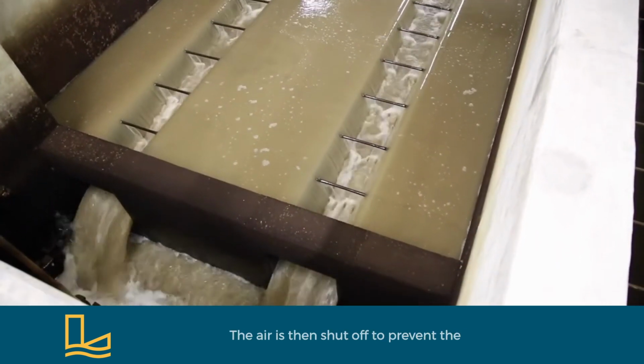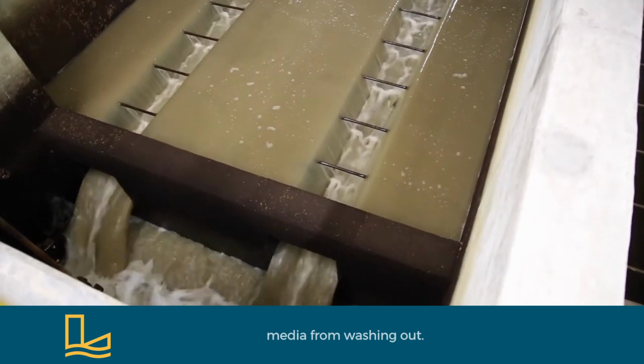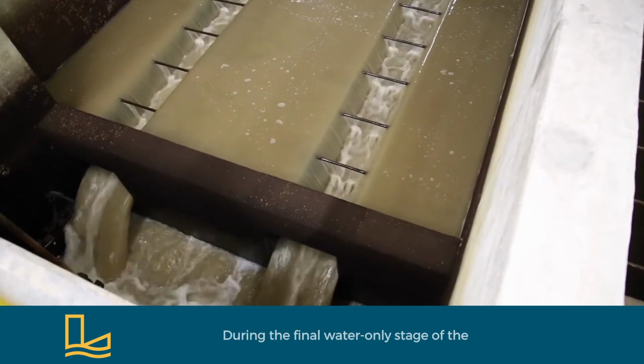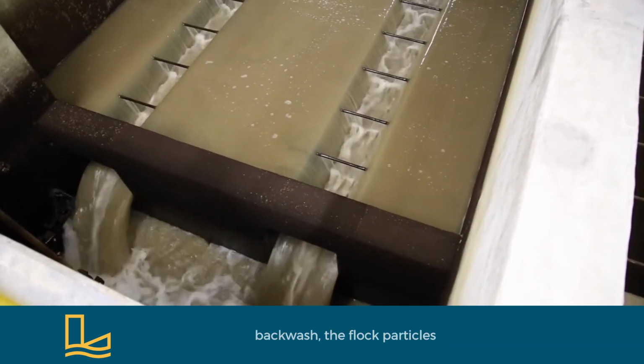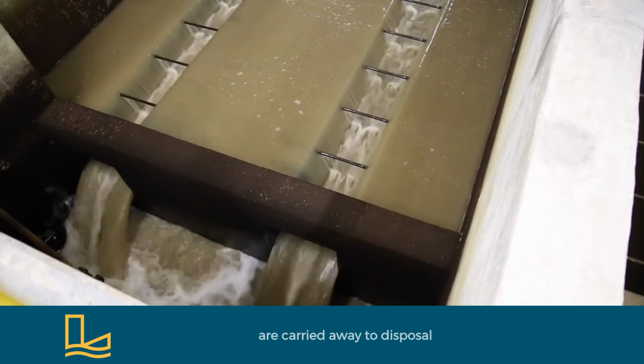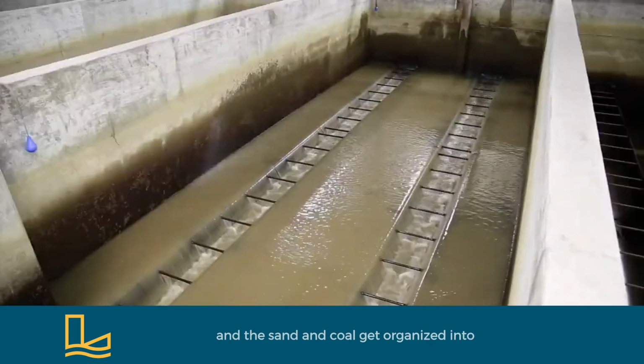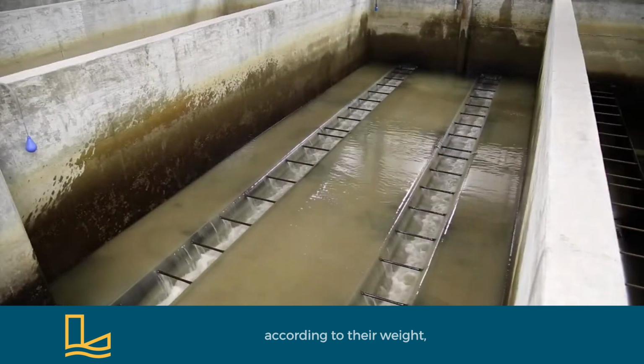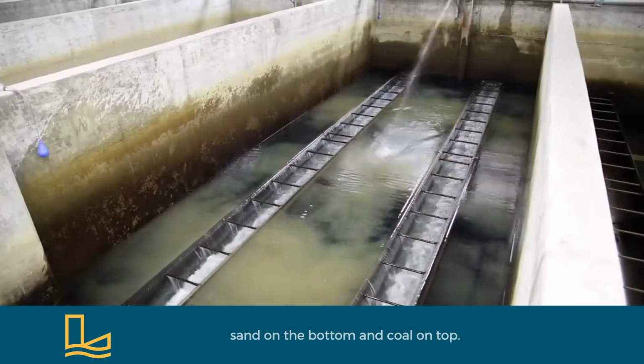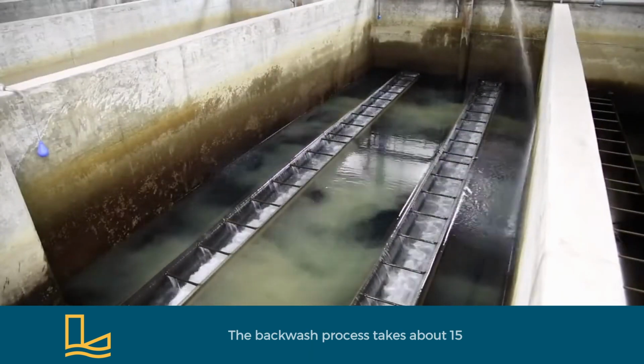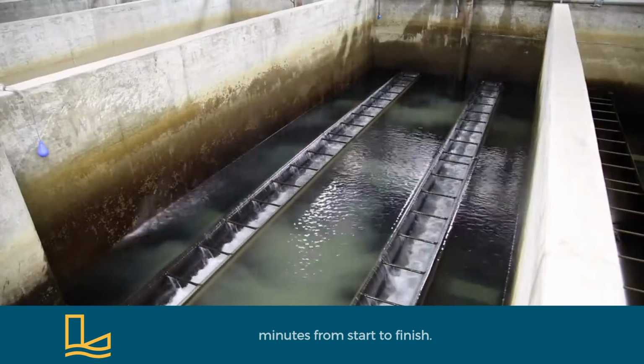The air is then shut off to prevent the media from washing out. During the final water-only stage of the backwash, the floc particles are carried away to disposal, and the sand and coal get organized into separate layers according to their weight, sand on the bottom and coal on top. The backwash process takes about 15 minutes from start to finish.